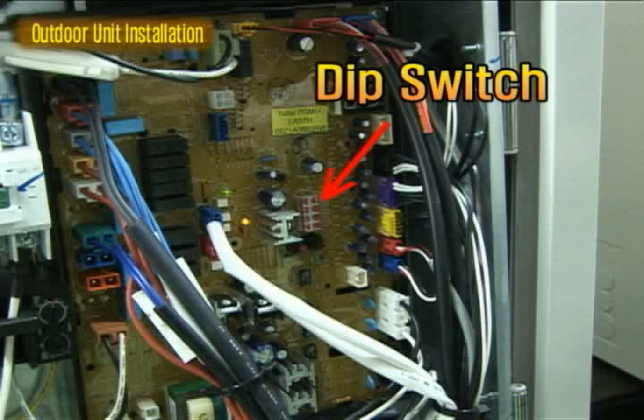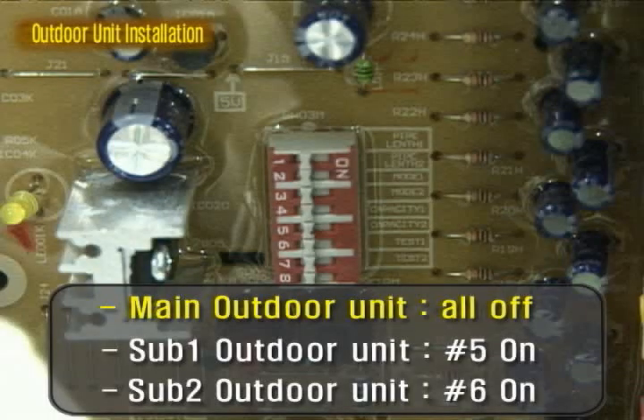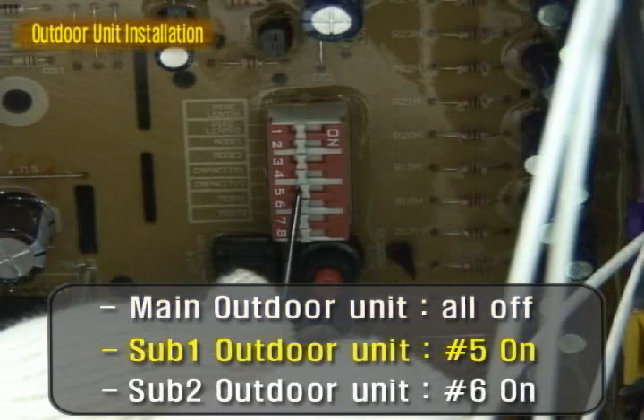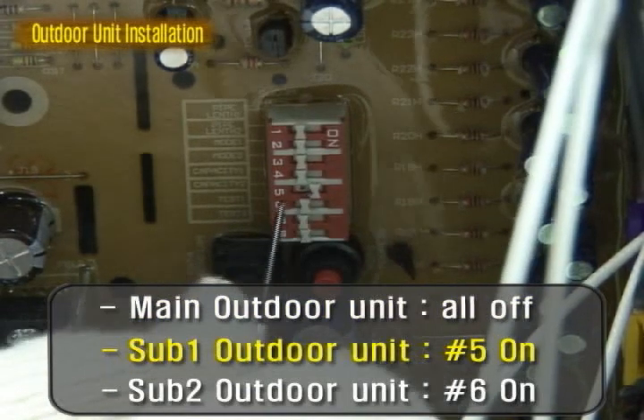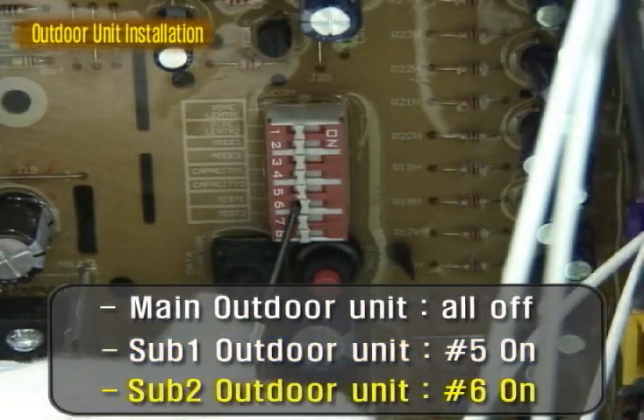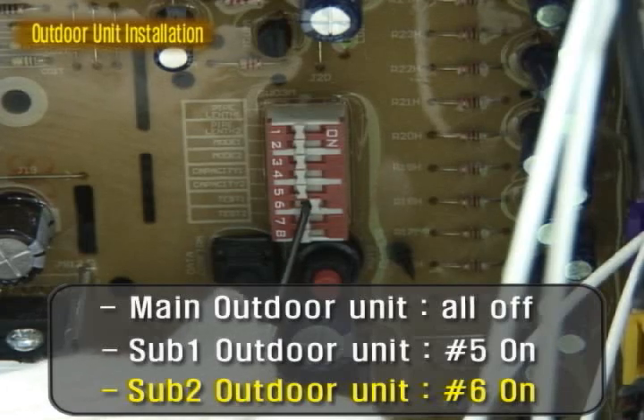If outdoor units are more than 2, set the dip switch for combined operation. For the main unit, set off all 8 switches. For the first subunit, set number 5 switch on. For the second subunit, set number 6 on.